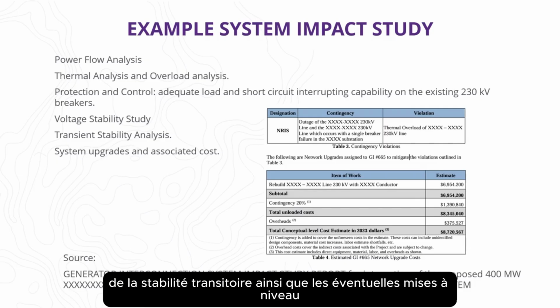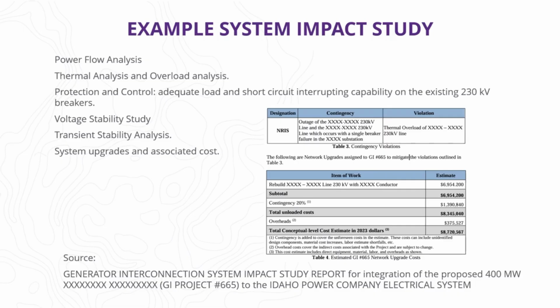There's also protection and controls, where the study surmises there's adequate load and short circuit interrupting capability on the existing 230 kV breakers. There's a voltage stability study, a transient stability study, and any system upgrades and associated costs are outlined in this report. The estimate for additional cost comes to something like $8 million plus.